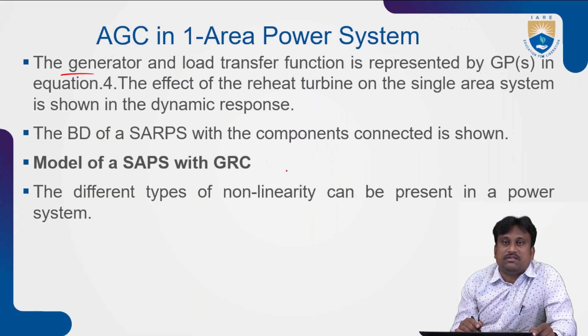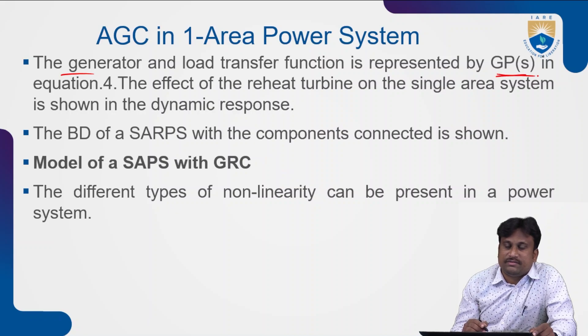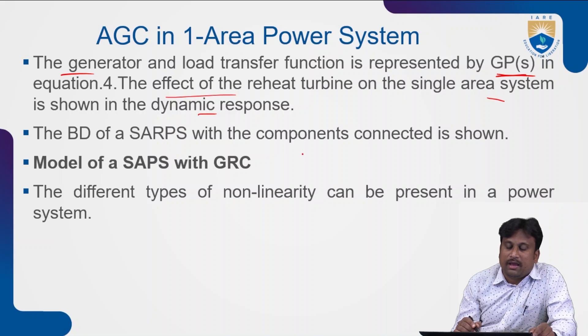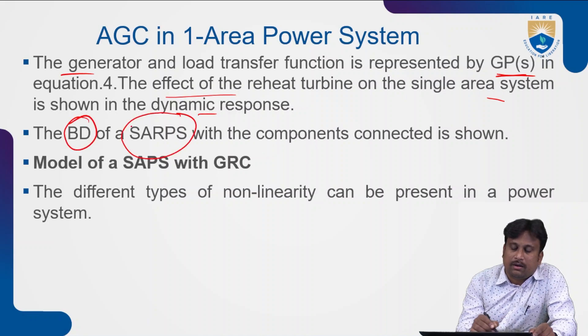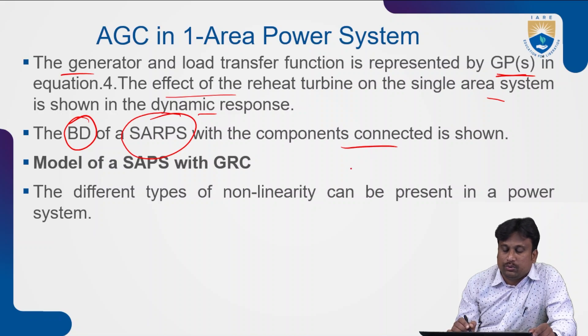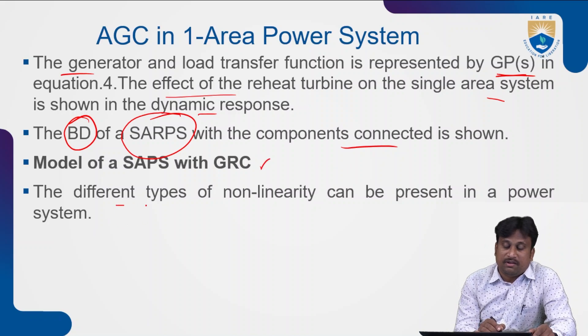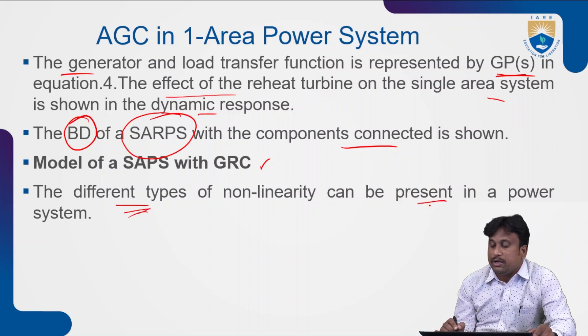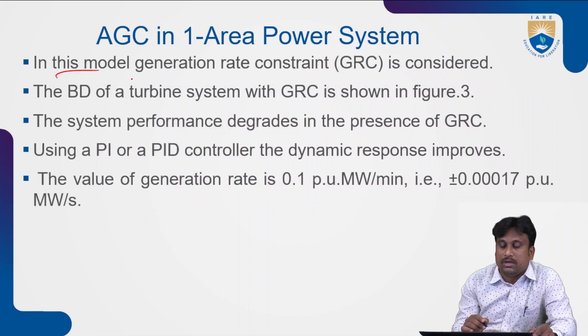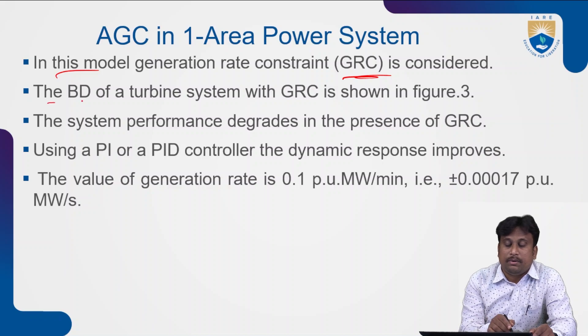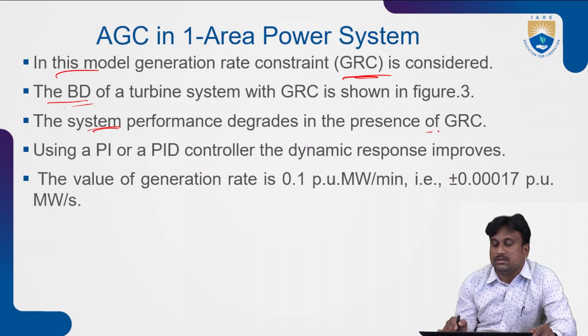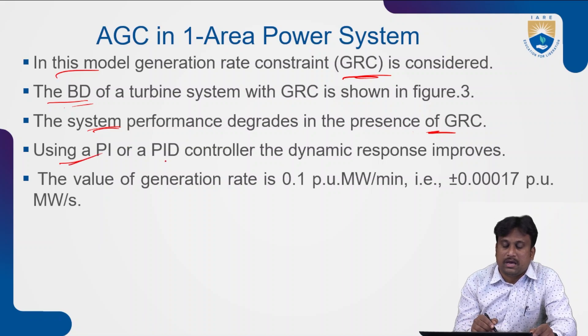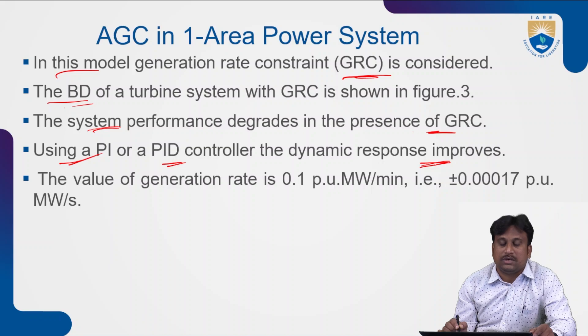The generator and load transfer function G_P(S) has already been seen. The effect of the reheat turbine on the single area power system gives a suitable dynamic response. The transfer function of the non-reheat turbine is GT(S) = 1/(1+ST_T), while the reheat turbine transfer function is GTR(S) = (1 + S*K_R*T_R) / ((1+ST_T)(1+ST_R)). G_P(S) is considered as KPS/(1+ST_PS). In the SAPS model with generation rate constraint (GRC), system performance degrades in the presence of GRC, and using a PI or PID controller improves the dynamic response. The GRC value is 0.1 pu MW per minute, approximately ±0.0017 pu MW per second.